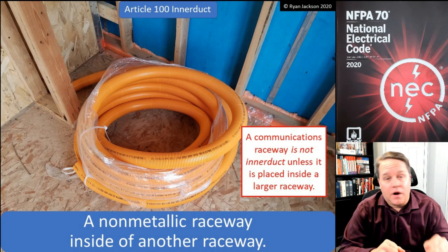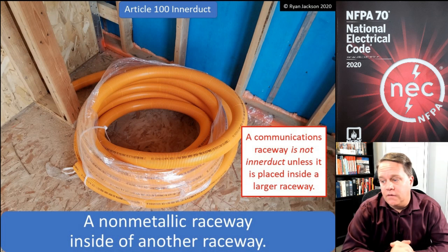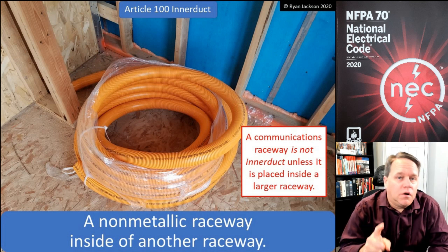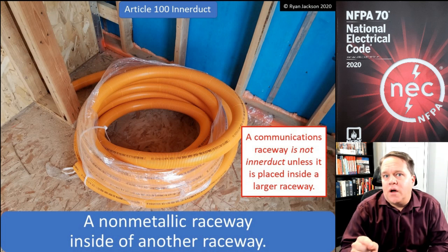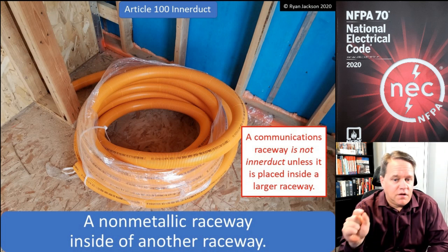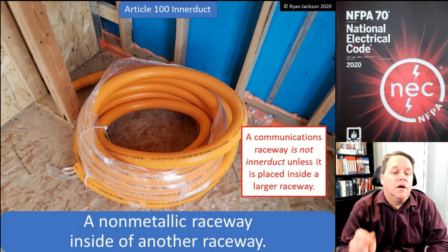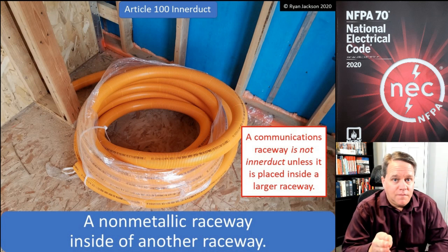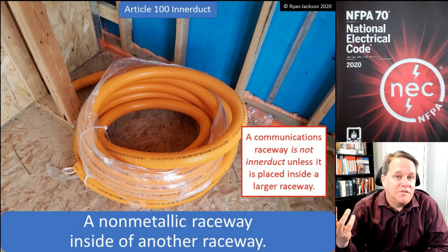I could use the product in this photograph as innerduct if I installed it inside of a piece of PVC conduit — that would make it innerduct. But if I installed it by itself, it's not innerduct, because innerduct isn't the product, it's the way the product is installed. It's a non-metallic raceway installed inside of another raceway. So that would be a communications raceway — I could use it as innerduct, or I could just use it by itself.